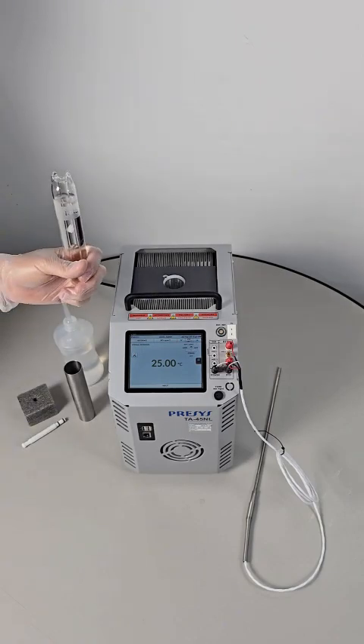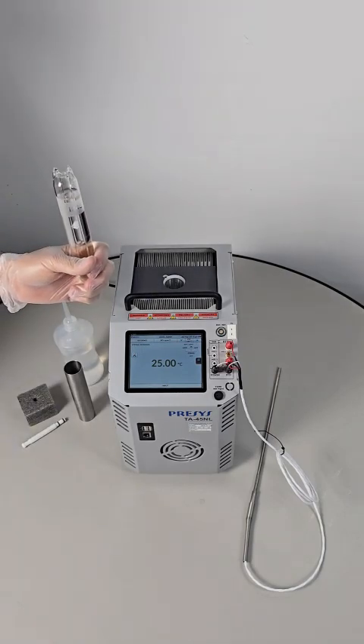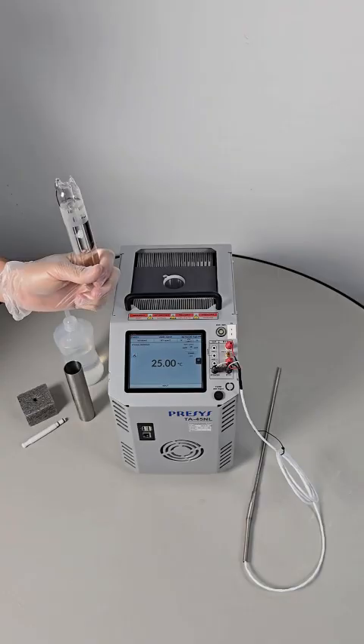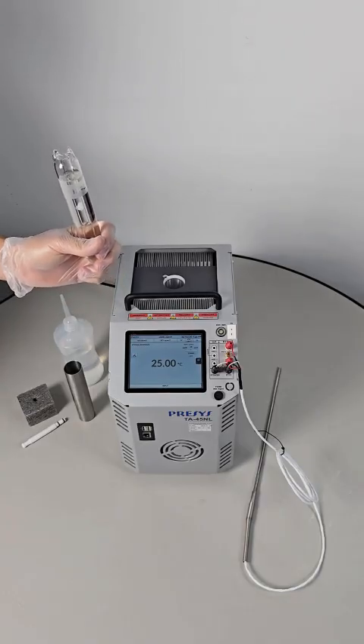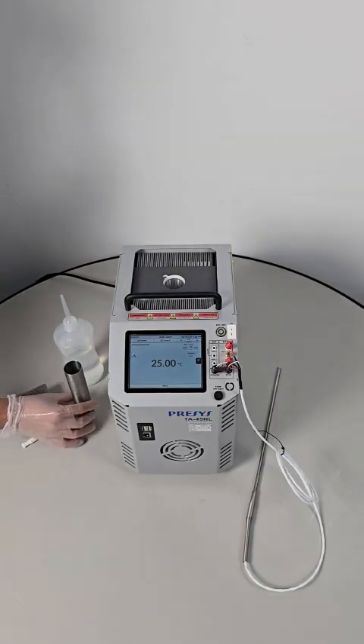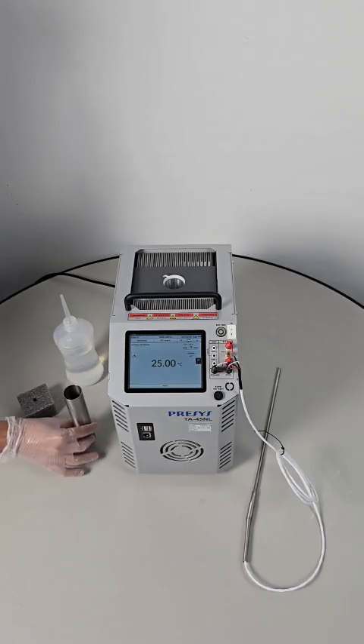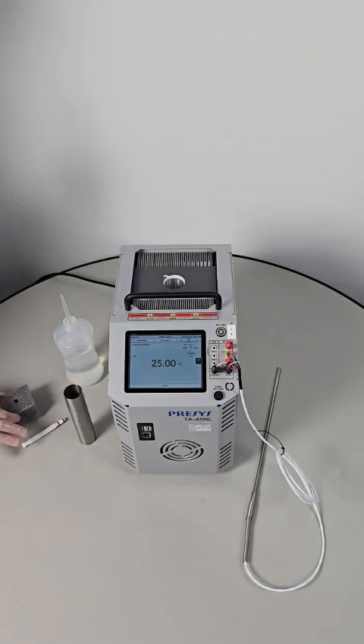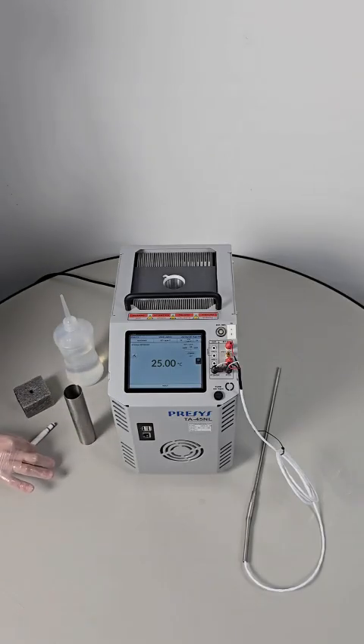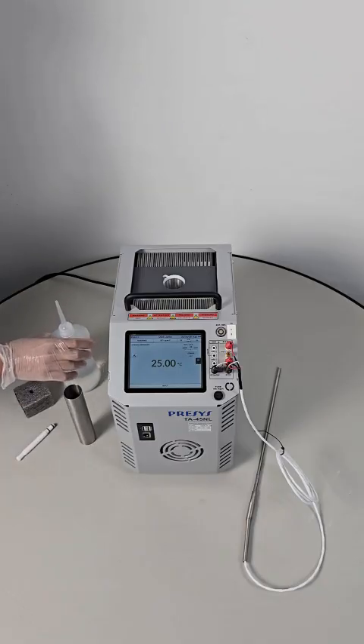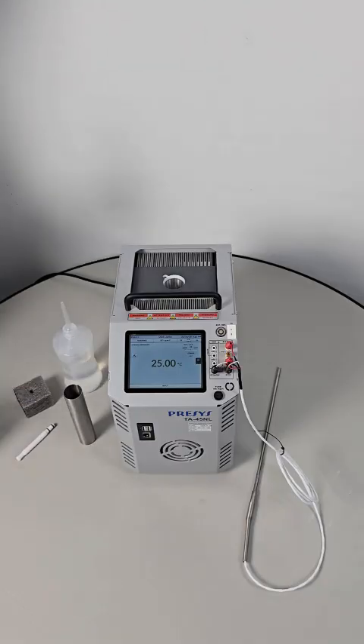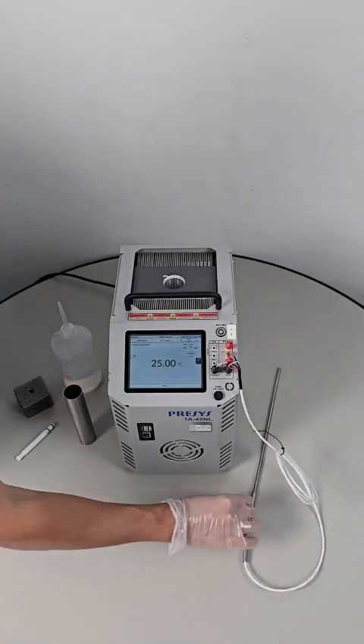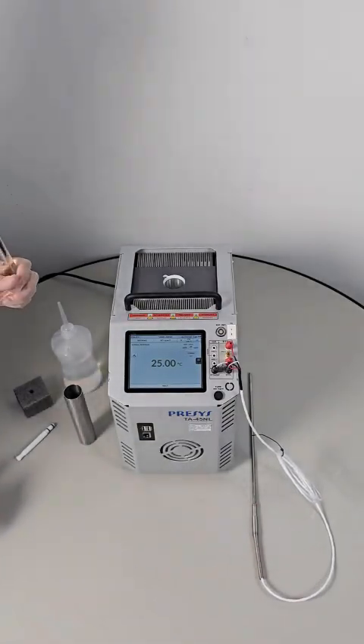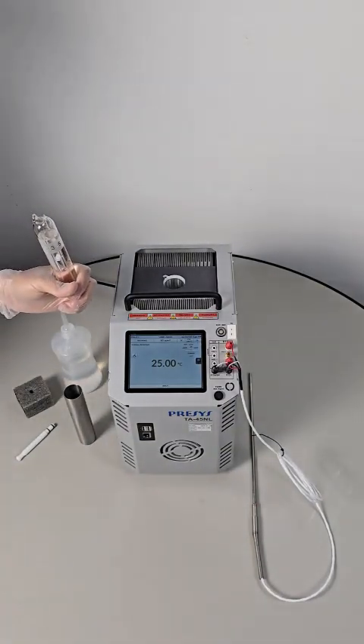To realize the water triple point, we will use a water triple point cell, an insert basket for housing the cell, an upper thermal insulation lid, an extractor for safe cell removal, analytical grade ethanol, to fill annular spaces and act as a heat transfer medium, and a standard resistance thermometer connected to the TA-45NL auxiliary input for monitoring.